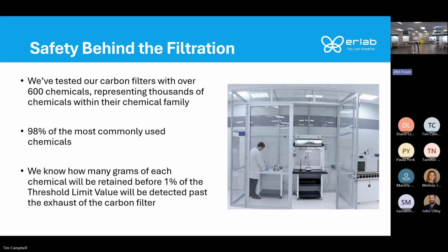So what we do when we're testing a chemical is we set up a filtration column. There's a ductless fume hood in that glass bubble or the test bubble. There'll be a main and backup filter on the ductless fume hood. Inside the hood, there is a hot plate with a dish. We then have a peristaltic pump pumping the chemical we're testing that day onto the hot plate, which is, as I said, inside that ductless fume hood. So it evaporates. That chamber is then sealed and the air inside is constantly sampled by a GCMS. This test can take from a couple hours to a couple days, depending on the chemical we're testing and the exposure level of that chemical. And we'll continue the test until we detect 1% of the threshold limit value of the chemical we're testing in the airstream past the carbon filters.